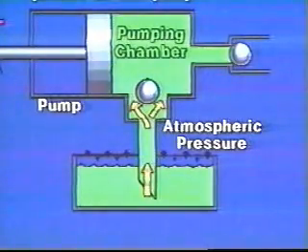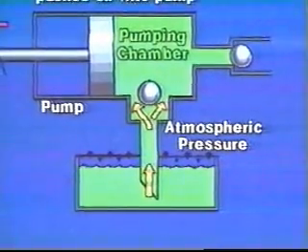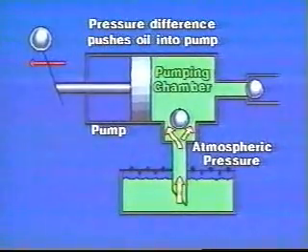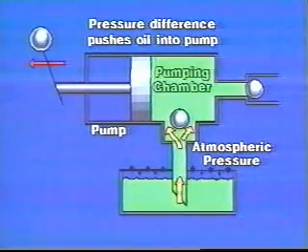It doesn't. A pump merely lowers the pressure at its inlet, and fluid is pushed in by the atmospheric pressure acting on its surface. Inlet lines are especially important because with only 14.7 pounds per square inch doing the pushing, any restrictions or even too thick an oil may cause the pump to starve. The technical word for this starving is cavitation, and it causes an erosion-type damage within the pump. An air leak at the inlet causes similar problems.